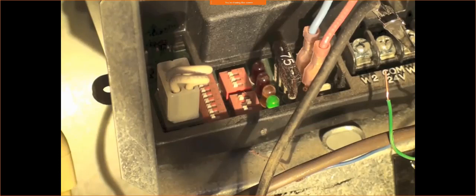Okay, now this code here is a 14 code. And what that means is it's gone into hard lockout, it could not light the burner. So this is a gas issue. There's either gas not getting there or it's not being sensed.